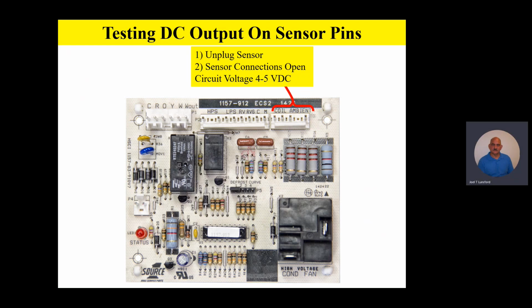However, on the other side of that coin, if you do have 24 volt AC between C and R on the board, and you do have 4 to 5 volt DC on the coil and ambient sensor pins, together and individually, then you know that the board is probably okay. Let me say it one more time. If you've got 24 volts going to the board and you have 4 to 5 volt DC on the sensor pins, then the board is probably okay.